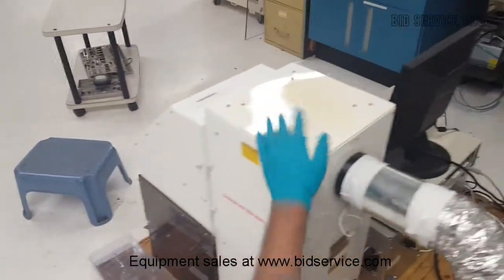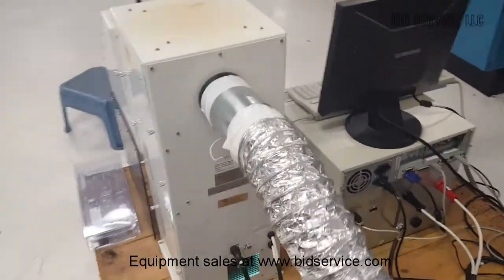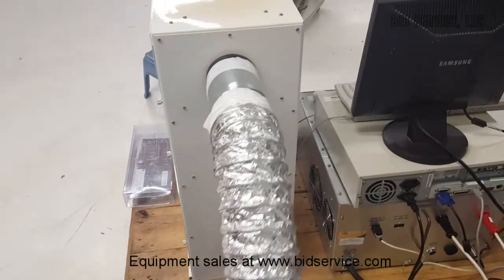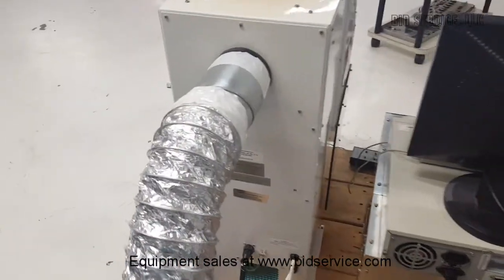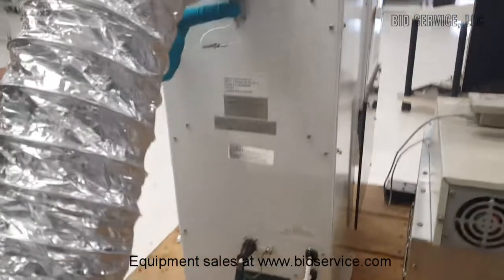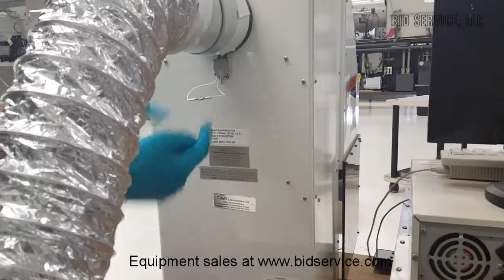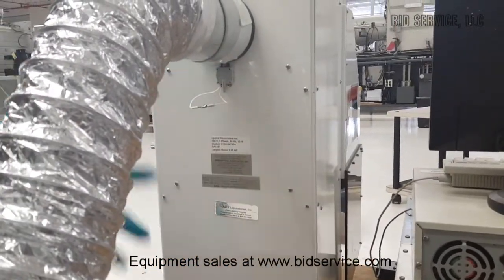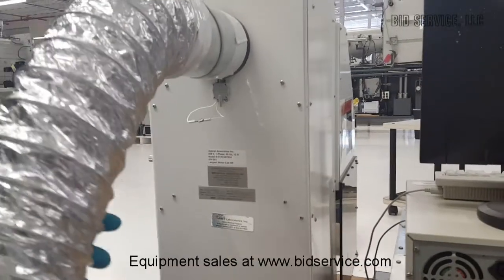So for the lamp housing cooling, I have used my in-house exhaust connection. This exhaust connection is slightly on the edge, on the lower side. This is the vacuum switch. I have jumpered it because my exhaust fan is not strong enough.